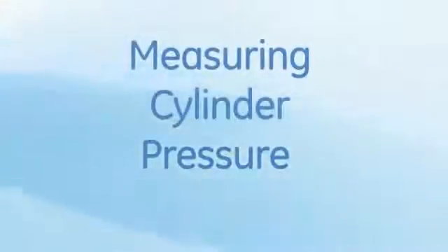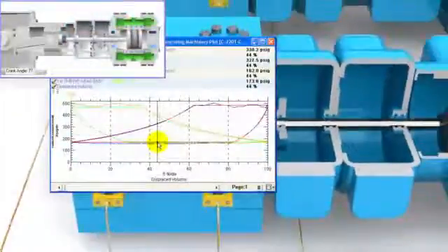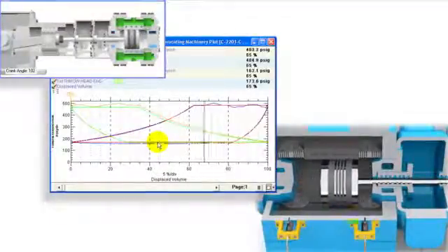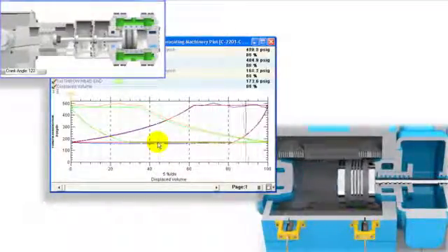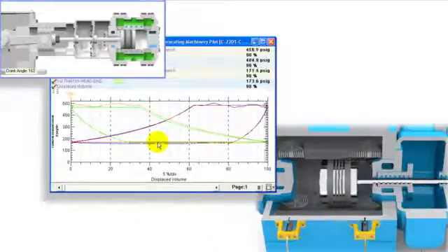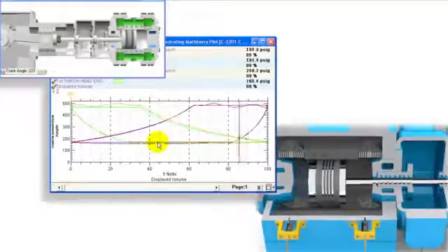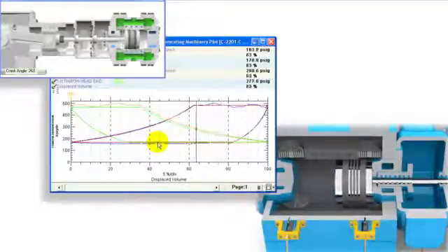Cylinder pressure is the single most important measurement for condition monitoring of reciprocating compressors. Equipped with accurate cylinder pressure at each point in the piston stroke, a pressure volume curve can be constructed that provides indispensable information on machine health.